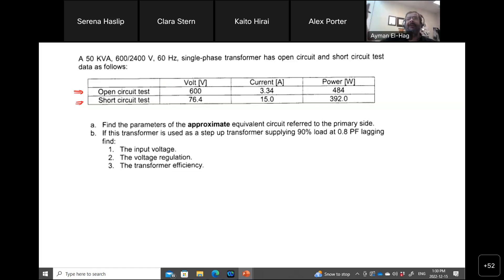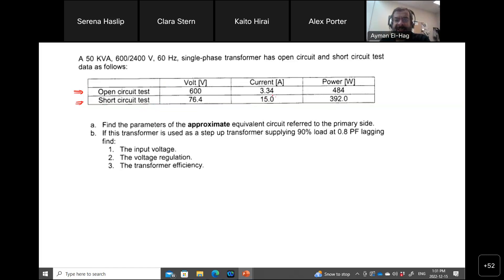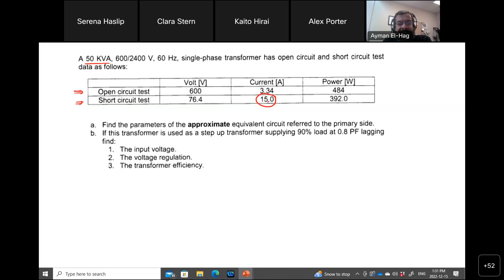The open circuit test is referred to the primary. For the short circuit test, on the other hand, by default if one side is given from the primary, the other one would be given from the secondary. Just to confirm, the current of 15 A is close to the rated current. This is a 50 kVA transformer — if you divide 50 kVA by 2400, you find the rated current in the secondary.